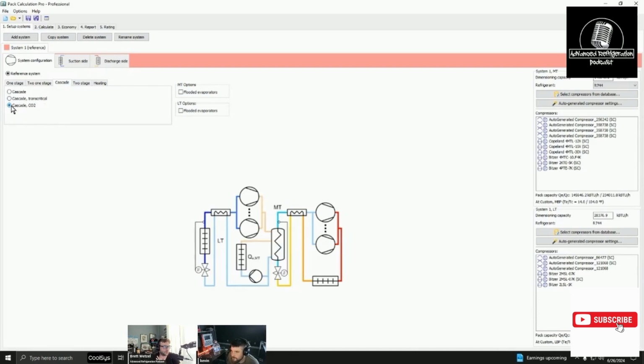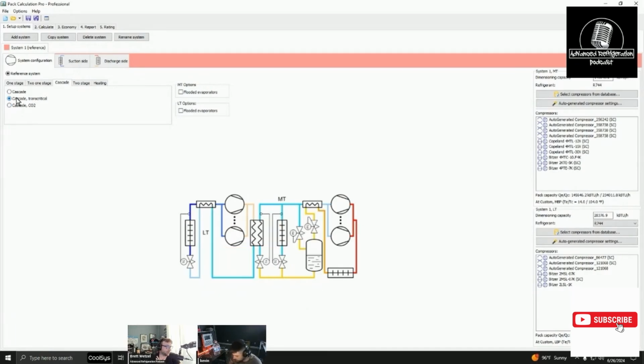So here we have CO2 cascade, so it looks like - oh yeah, so you can select a different refrigerant for the primary, and then it's just CO2 for the secondary. And then you have, so that would be your Targets and Walmarts, or HEBs, right? And then you have cascade transcritical, so you basically have a regular transcritical system here being the condenser for the low temp. So I guess you have a lower condensing temperature.